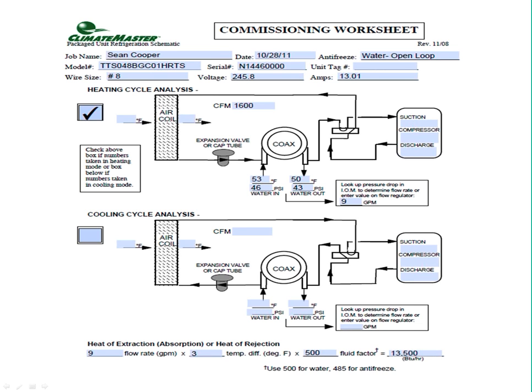So at the very bottom of the page, guys, you'll notice that we're going to finish up our formula here. So we're going to put our flow rate in there of 9, then our temperature difference of 3, the fluid factor of 500. We're going to calculate that out. Again, it shows you at the bottom of this page, use 500 for water, 485 for other than water, in other words, antifreeze. In this case, we're extracting 13,500 BTUs, which is low.